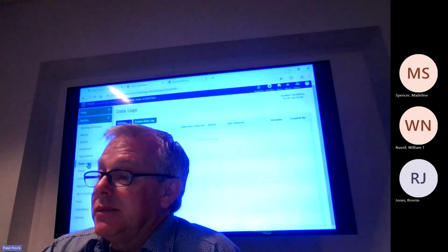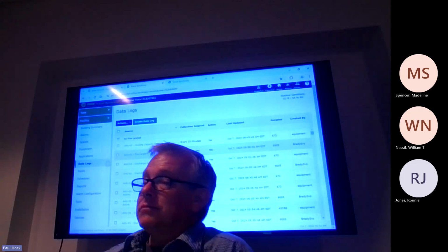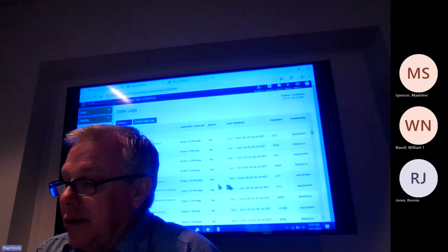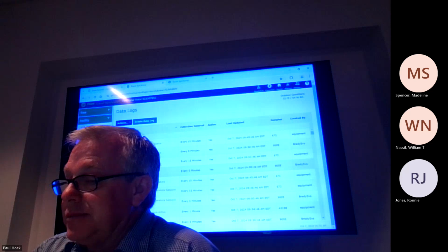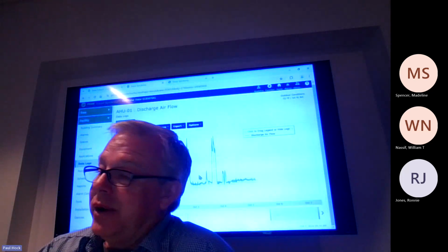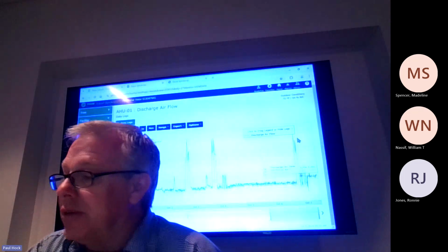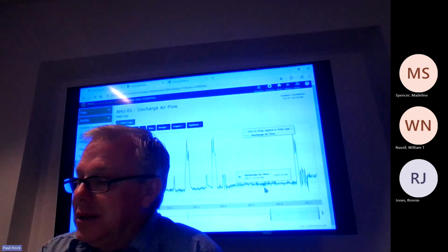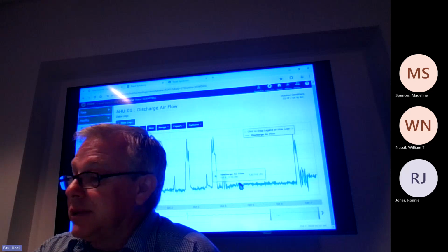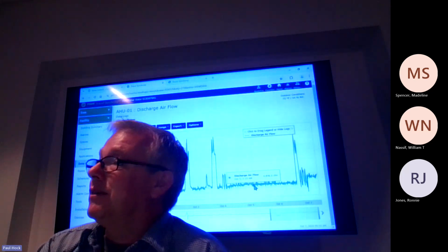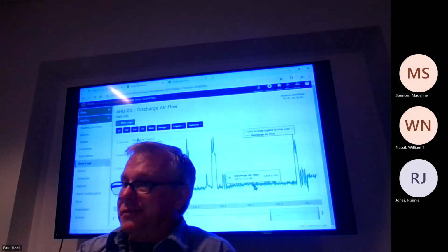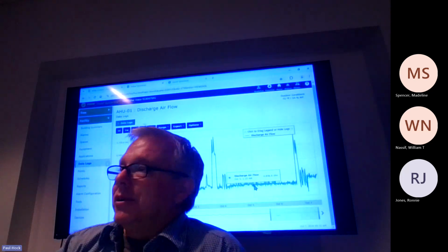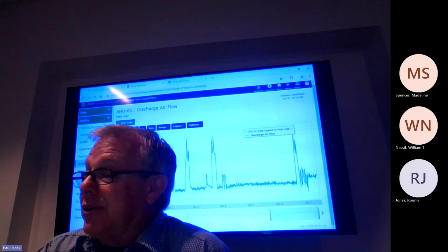And we've got data logs, so the system does log almost every point in the system. You can create data logs if you don't see it. So like air handler one, discharge air temperature. If you want to find out when it died, on what specific date, you can nail it down to a specific time. And sometimes you can call Duke and say, hey, what happened at this time? Did you have a power issue? Yes, we did. That way you can find out if it was a Duke issue or something else is going on with the site. I use this a lot for troubleshooting.